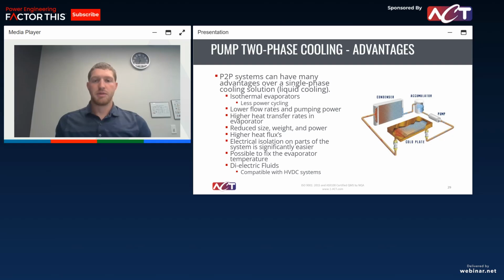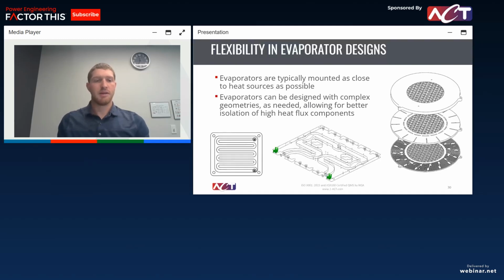Kind of similar to loop thermosyphon, our dielectric fluids and our electrical isolation make that part of the system design a lot easier. You don't have to make sure that you're not conducting into your water or into your fluid and into your system, with all the refrigerants we use being dielectric and compatible with HVDC systems.